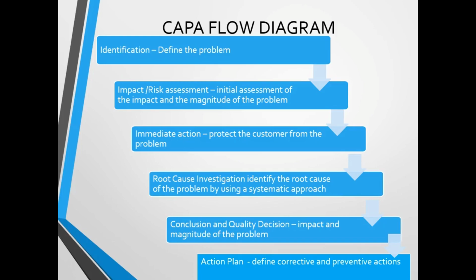And it's not listed here, but during FDA audits or any regulatory audits, the focus would not only be on the action plan, but the implementation and the follow-up. So it would always be checked to make sure that your action plan has been executed and that all tasks have been completed to prevent recurrence, that all actions taken were documented, and the appropriateness and effectiveness of the actions are evaluated. So have all recommended changes been completed and verified?